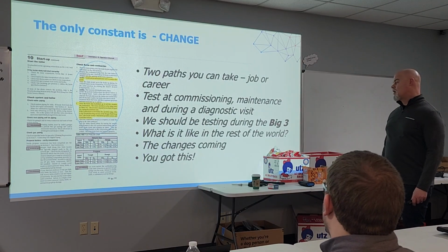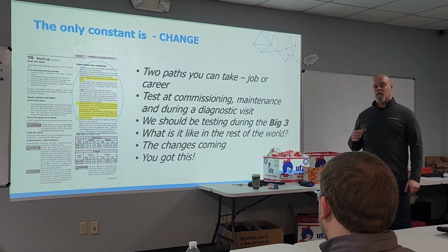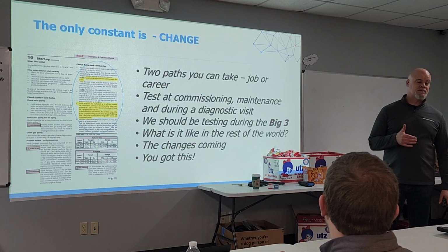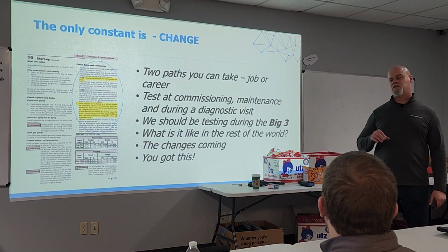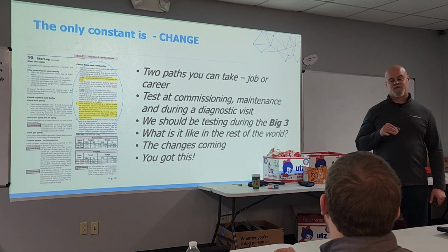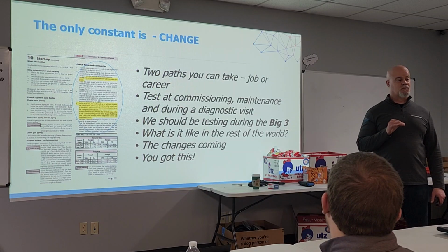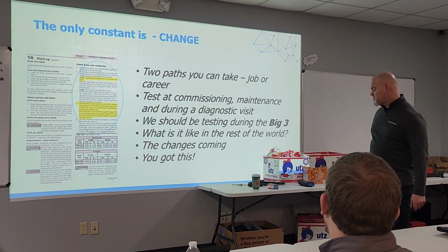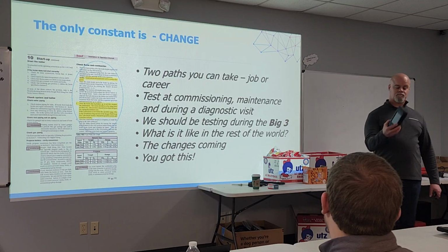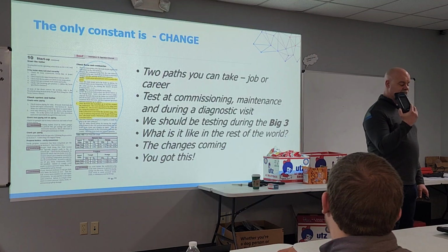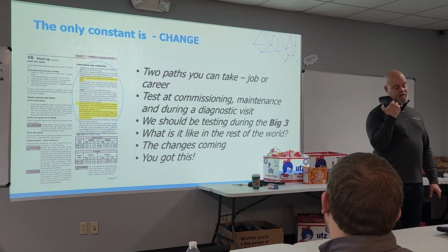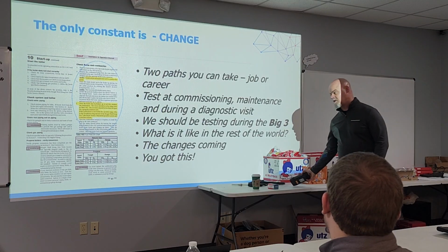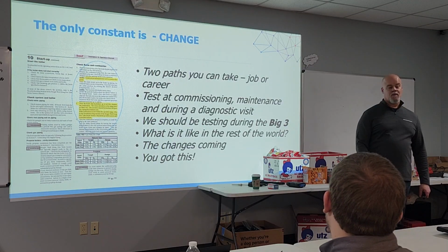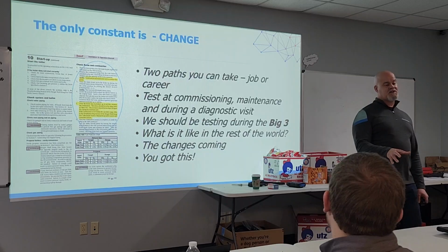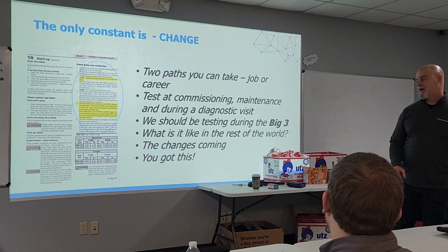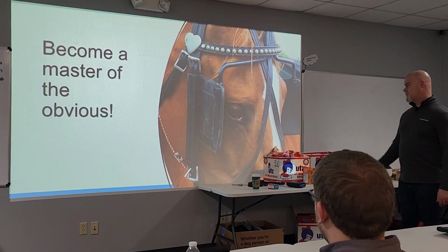The change is coming, and one of the biggest changes is low NOx. In Colorado, effective this past January 1st, only ultra low NOx furnaces and boilers are being installed - that's the new rule. The only way to properly commission a low NOx system is through a combustion analyzer equipped with a low NOx or NOx sensor. So for those that didn't want to test before, eventually you're not going to have a choice. You're going to have an analyzer - that's where this is going.